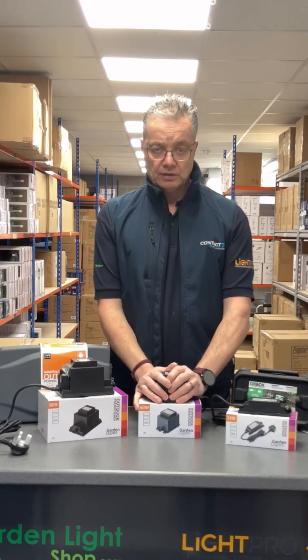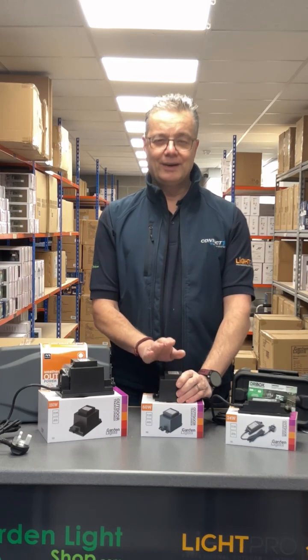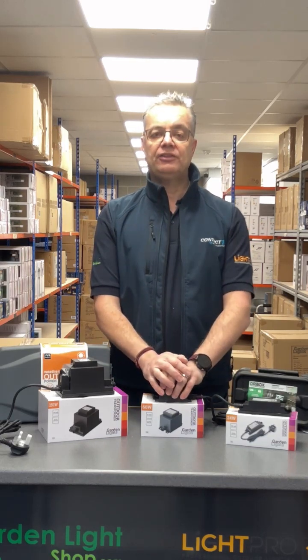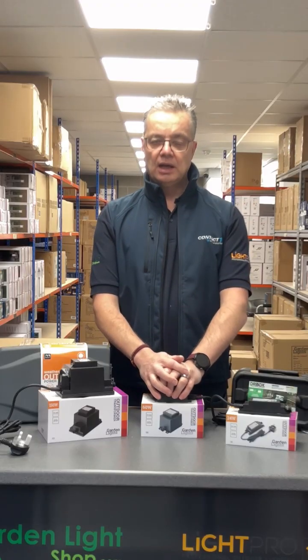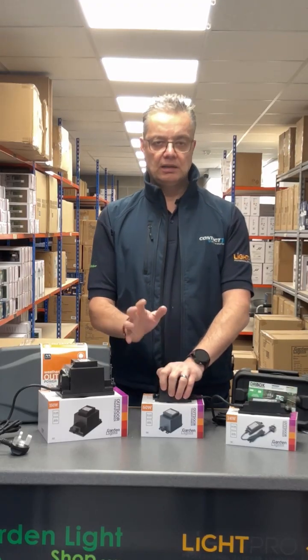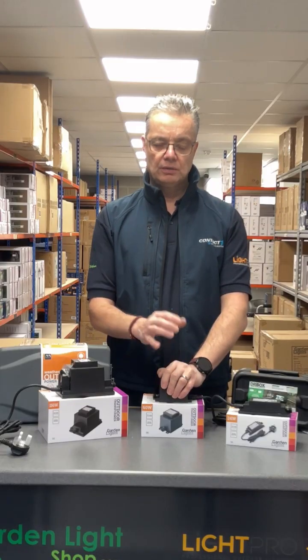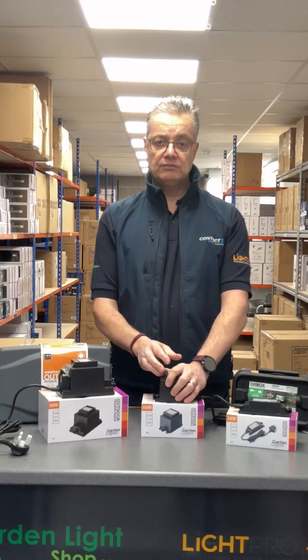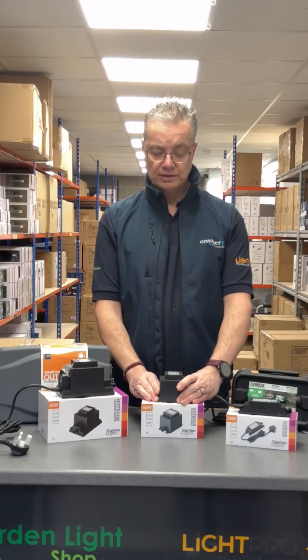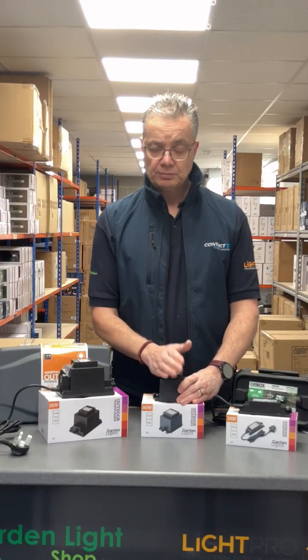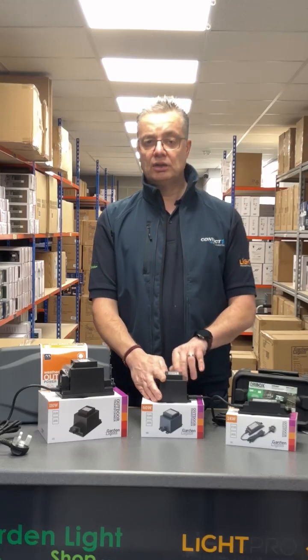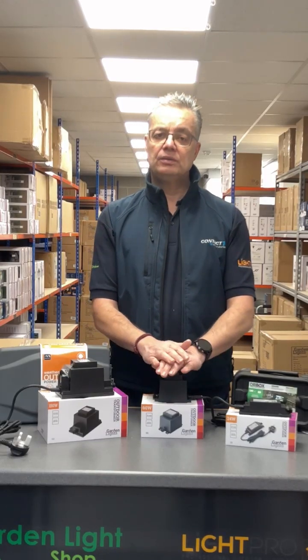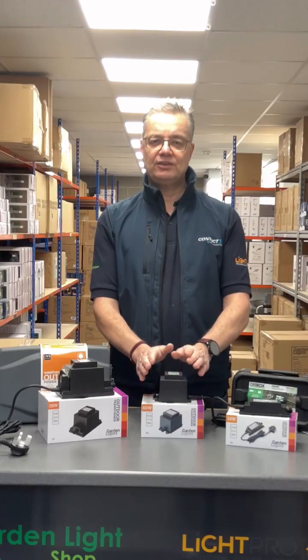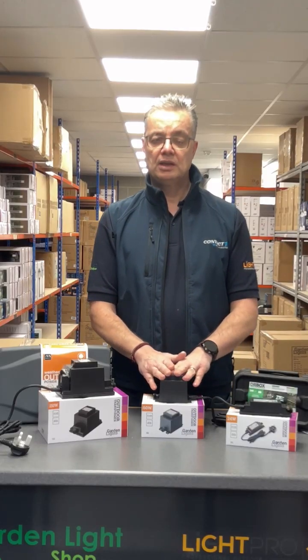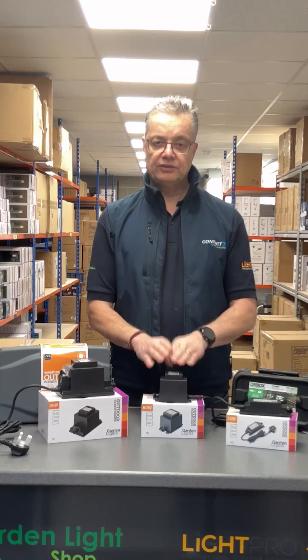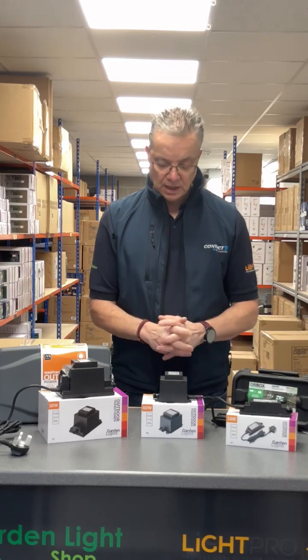Then we go to the 60 watt version, which sits in the middle. This is a 12 volt AC output, so it needs derating - you can't run this at 60 watts. With LED loading, and all our lights are LED, when you initially switch on the lights there's a very high inrush current associated with LED lighting, which for a split second puts this transformer under a lot of excess loading. So this needs to be derated by 25%, so you can only use 45 watts of this 60 watt capacity for LED lighting.